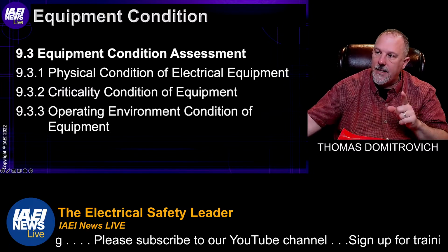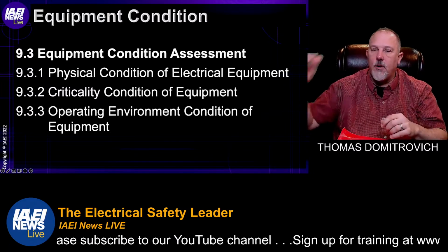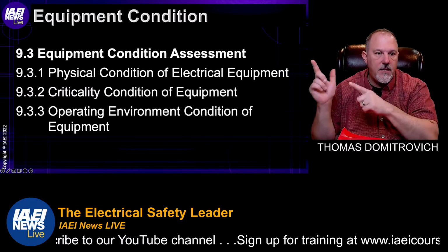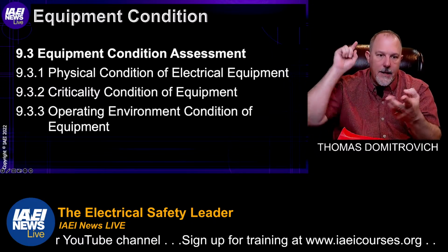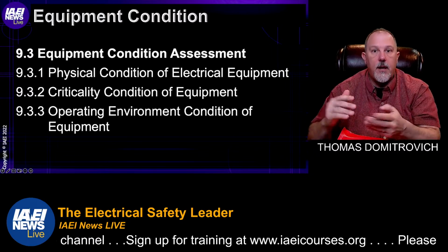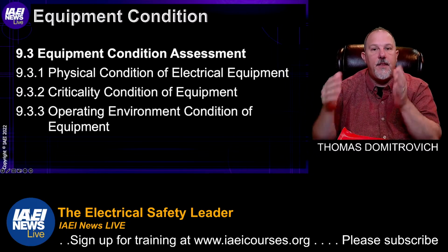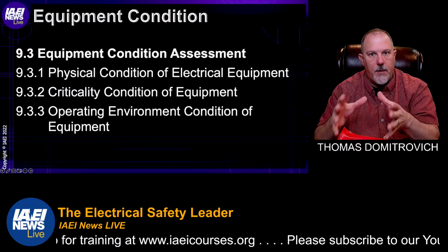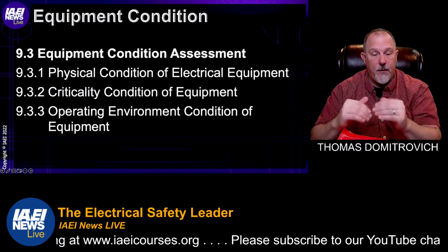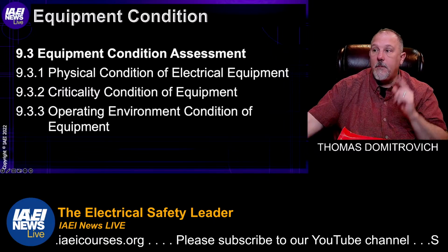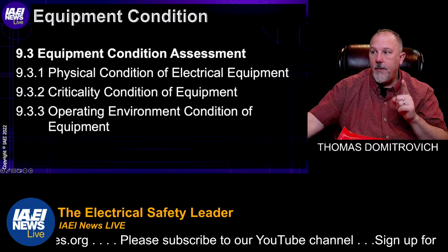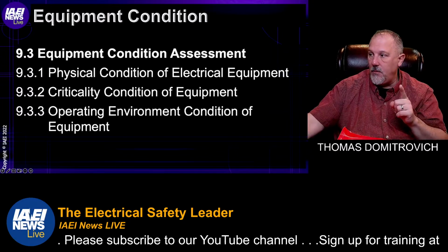So now I know the condition. I give it a 1, 2, or 3 for each of these: physical, criticality, and operating, whichever is the worst. And remember, the higher the number, the worse, so that's how I label that piece of equipment. And that's going to determine my frequency of maintenance. And for panel boards, remember, there is a frequency of maintenance table.